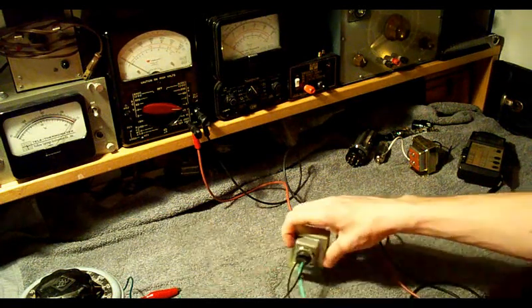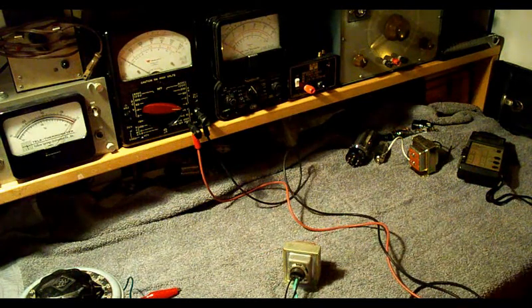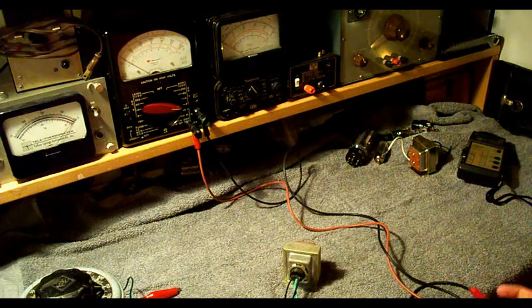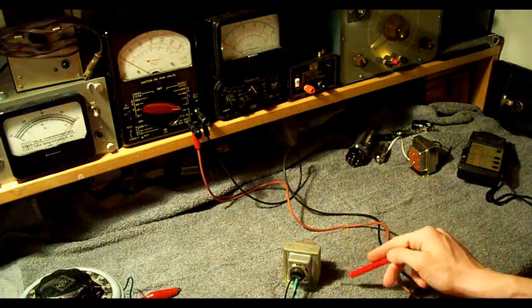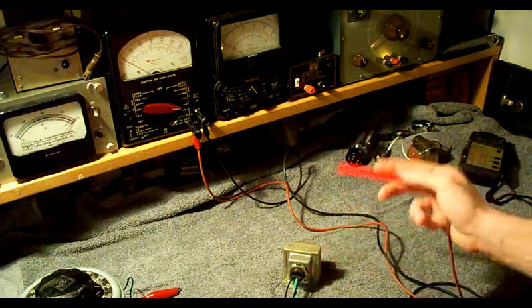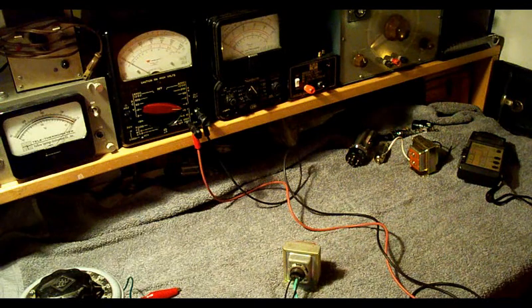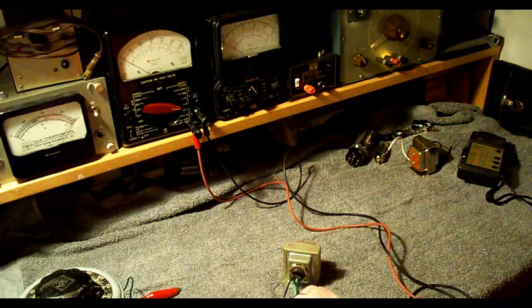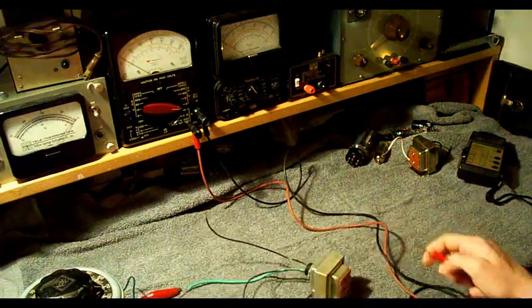Well, electrically in a transformer, none of the windings are supposed to ever be touching. So the primary winding is completely separate from the secondary winding in a transformer. The only indirect connection is through the actual iron core, where the magnetic flux causes a voltage to be induced in the other winding. So now we're going to go ahead and check one side of the primary to one side of the secondary.